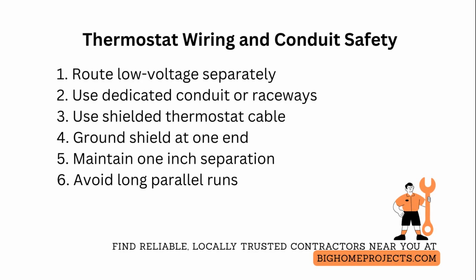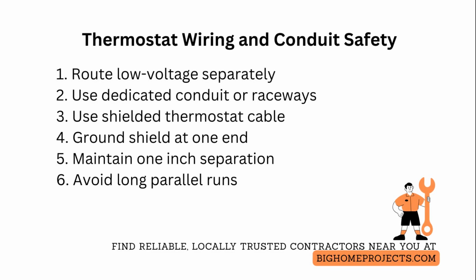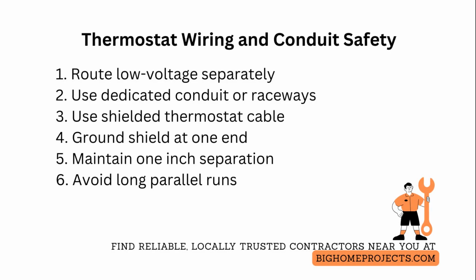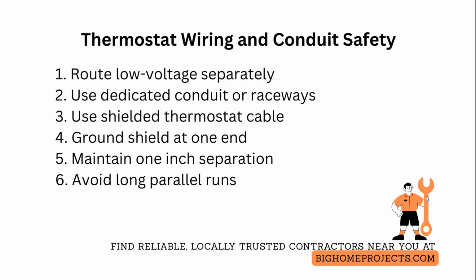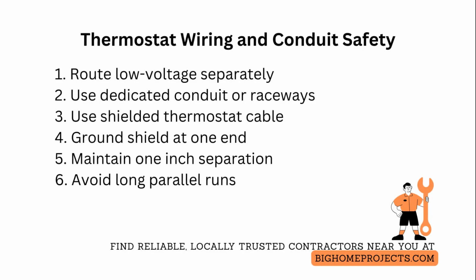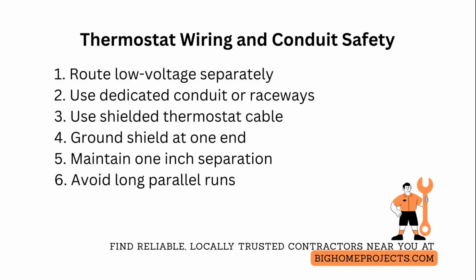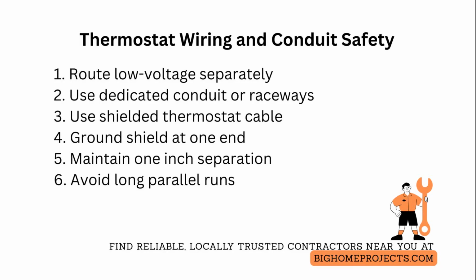guidance first. Choose thermostat cable with foil or braided shielding, and terminate shield to ground at one end only to reduce induced noise. Maintain at least 1 inch of physical separation inside junction boxes and use insulated, rated bushings where cables enter to prevent abrasion. Avoid parallel runs longer than 12 inches to minimize induced voltage and humming on sensors and control circuits.